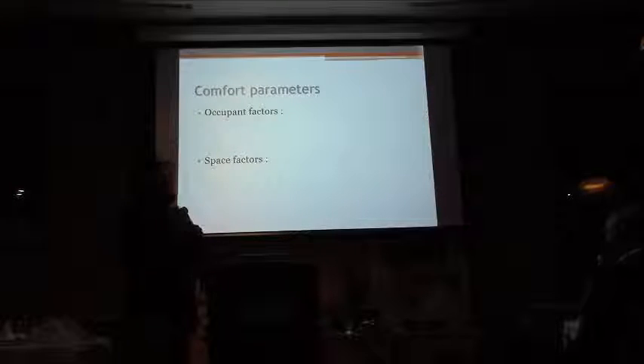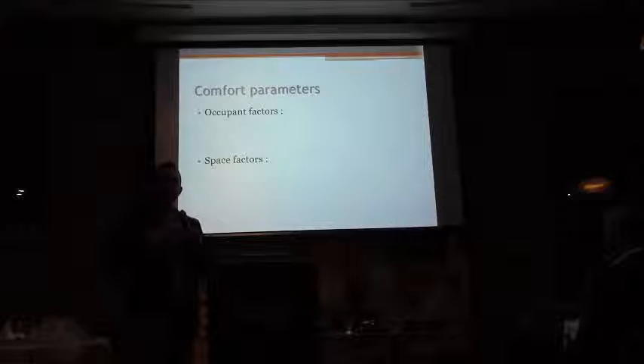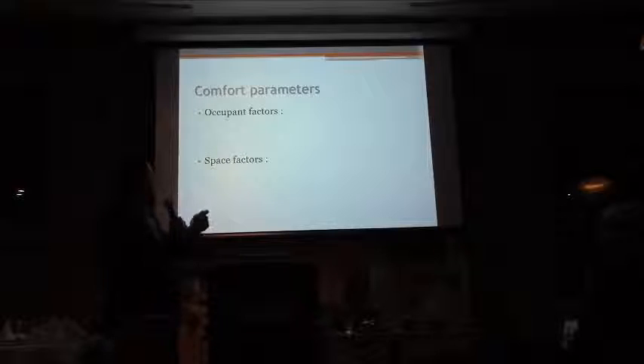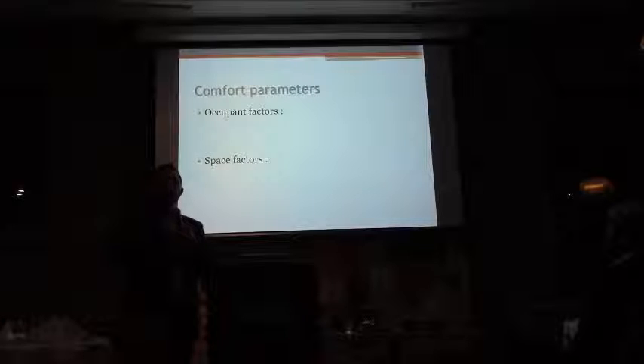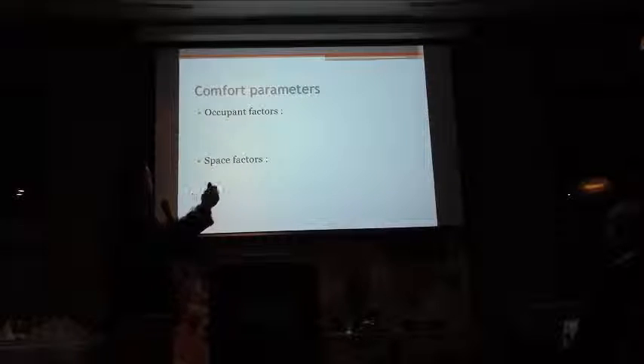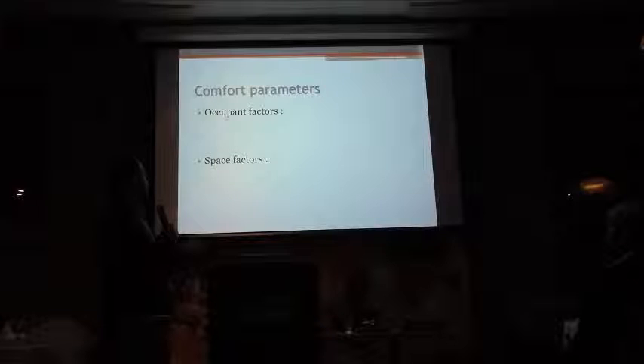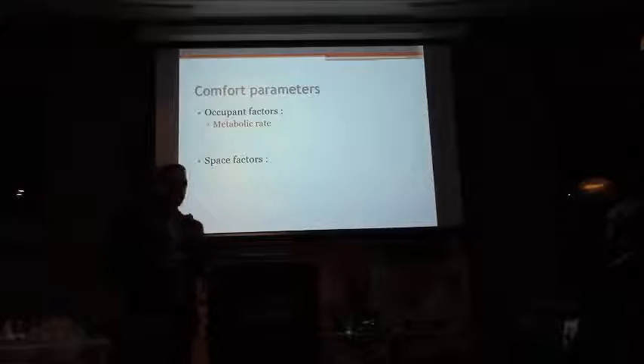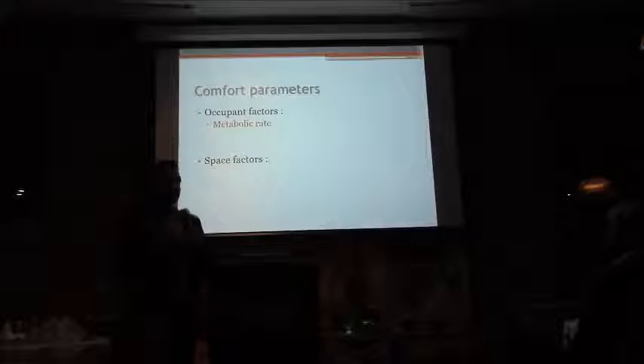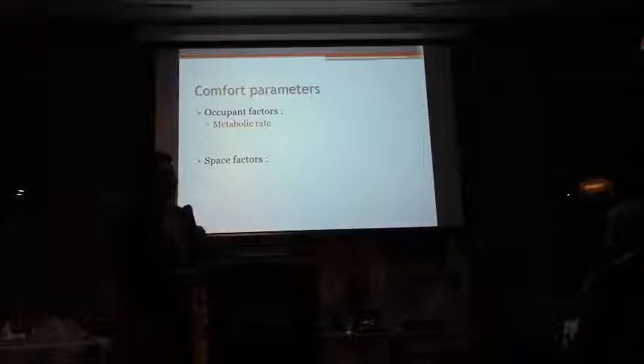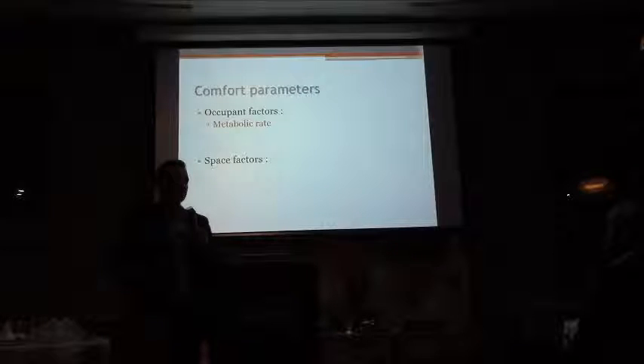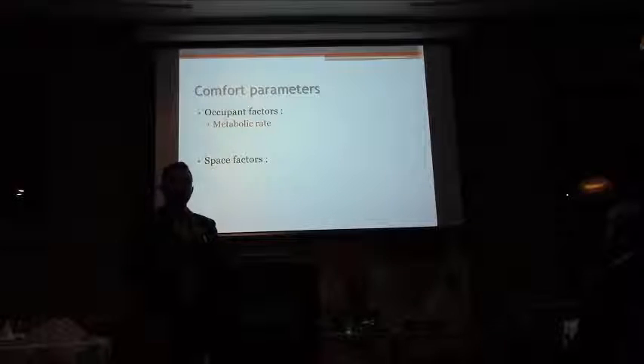So everything I just described is how your body can transfer heat to the environment, the mechanisms to transfer heat. And the comfort parameters are what control how much heat you transfer to the environment. There are occupant factors and space factors. The first occupant factor is your metabolic rate. Once you're designing a system, you have to ask yourself what you are designing it for. Is it a gym, where your metabolic rate is around 7 mets? Or an office application, where you're at approximately 1.1 to 1.3 mets?